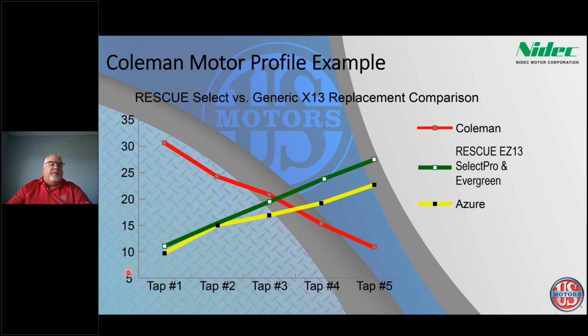I'm sorry, this is ounce-feet of torque. It's getting 10, and it really is expecting 30. You can imagine that motor is going to be running very slow compared to what it would be. What's that going to cause? Longer run times. I would argue if it's cooling and it's a humid environment, probably a frozen coil—all the things you don't want to have happen because the airflow is just so low.